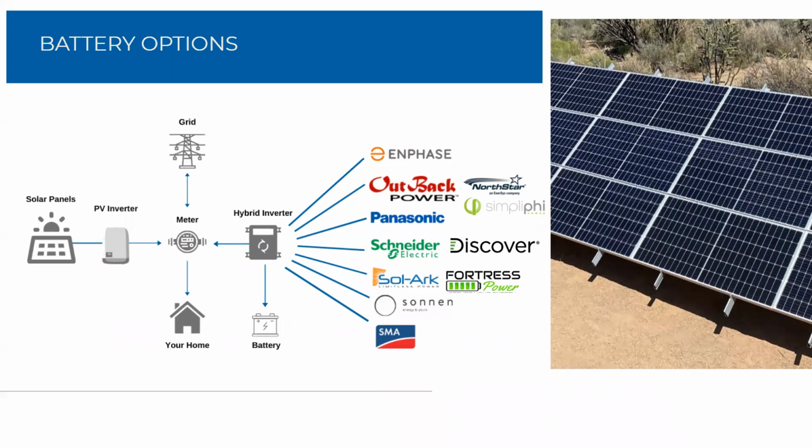If we want to take this one step further, all of these can be programmed manually and would just operate communicating via voltage. However, Fortress has closed loop communications compatible with Sol-Ark. That means that in addition to voltage, state of charge is also communicated to the inverter.